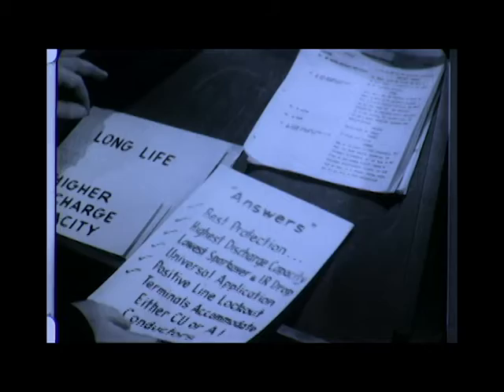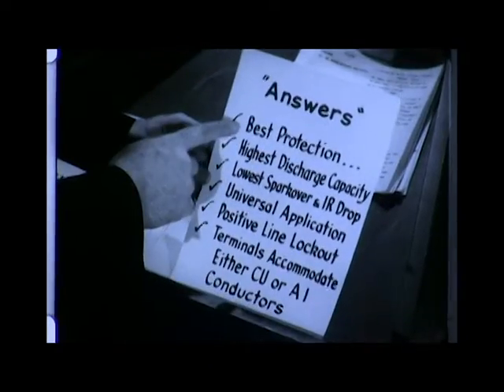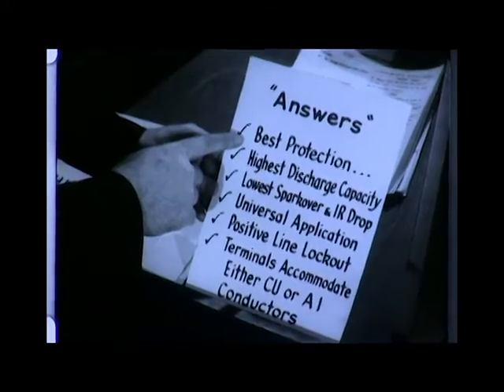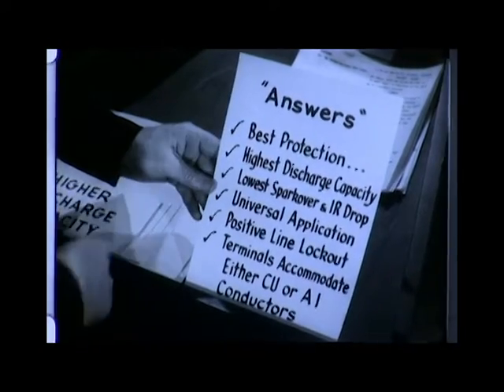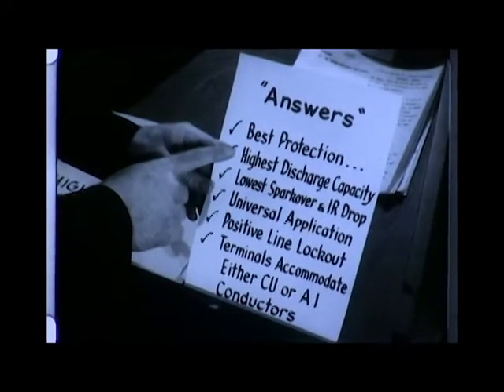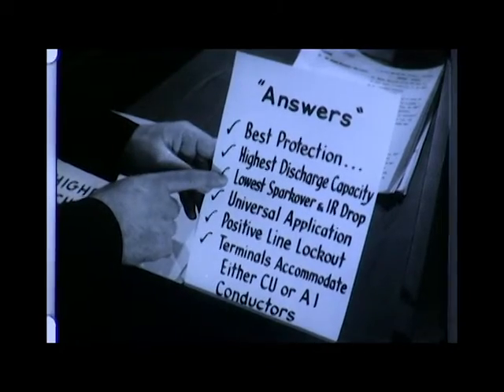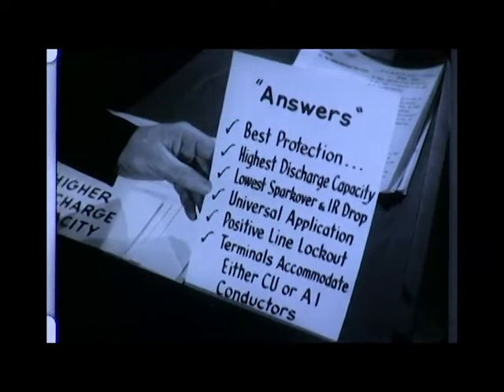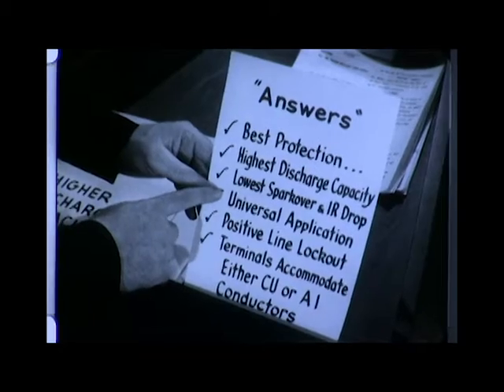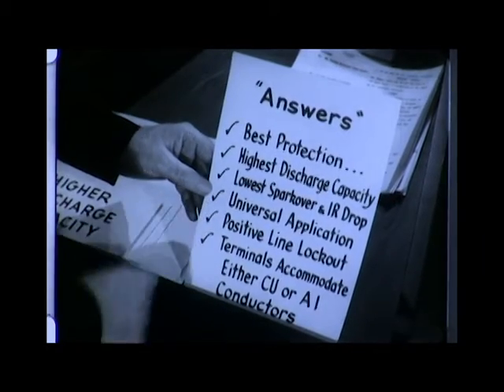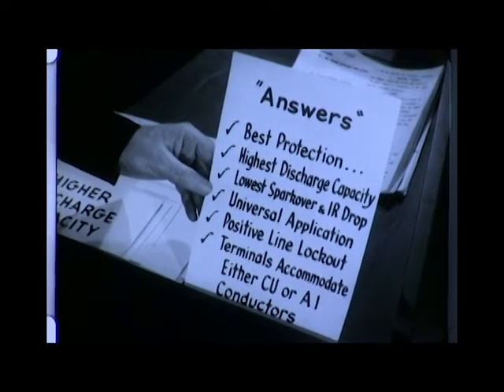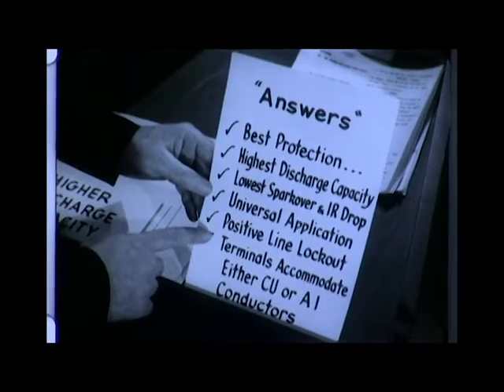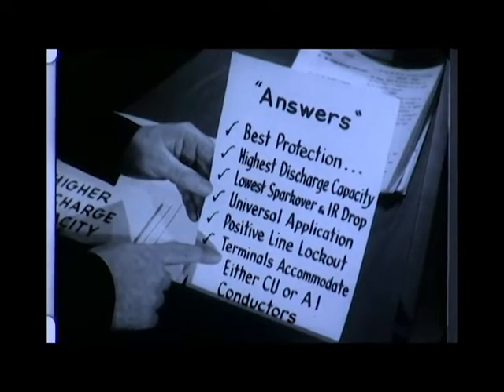The Magna-valve distribution arrestor offers the best protection, whether it be size, weight, spark over voltage, discharge capacity, or IR drop. It provides the highest discharge capacity and the lowest spark over and IR drop available in the industry. It has universal application, and positive line lockout is provided through either an external gap or a lead disconnector. The terminals can accommodate either copper or aluminum conductors.